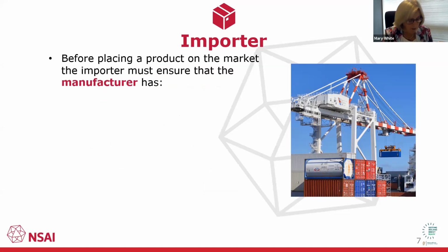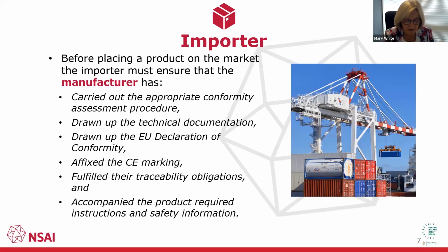The importer is responsible for ensuring that the manufacturer has met all their obligations set out in EU legislation. These include carrying out the correct conformity assessment procedure, drawing up the technical documentation, drawing up the EU declaration of conformity, affixing the CE marking, fulfilling their traceability obligations, and drawing up and including the required instructions and safety information for the product in the correct language.